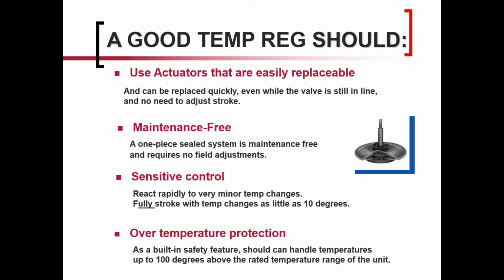So some things that a good temperature regulator should offer you, and you might have looked at the first picture and thought, well, that's a pretty simple device, and they are, but there's still some design features and attributes that should be available to anyone that applies these. For example, actuators that are easily replaceable. The actuator is usually part of the thermal system, so you want that to be replaceable easily. So ideally, the product can be replaced in line. You don't have to have any stroke adjustment, and that thermal system, inclusive of the actuator, is one part, for lack of a better term, so you don't want to weld capillaries, you don't want to weld sensing bulbs, you don't want to do anything like that. So the actuator assembly should be very easy to replace.